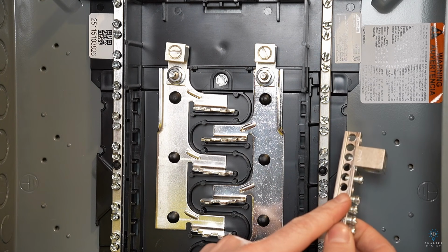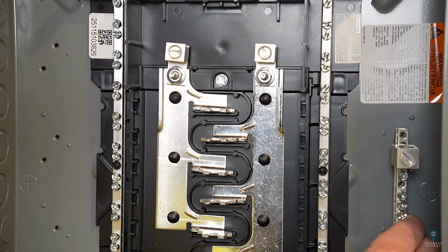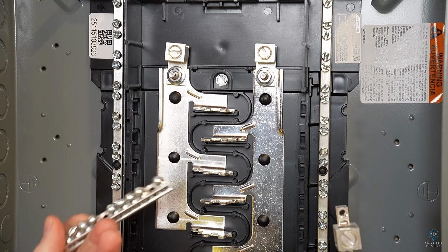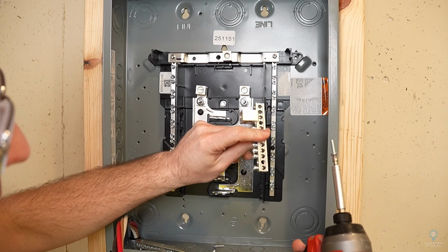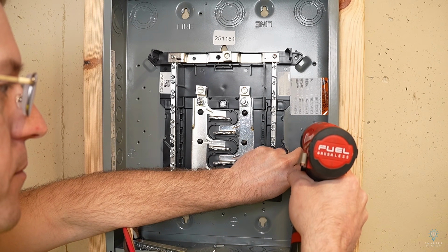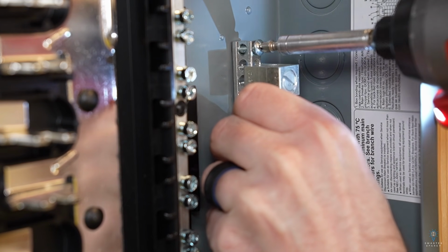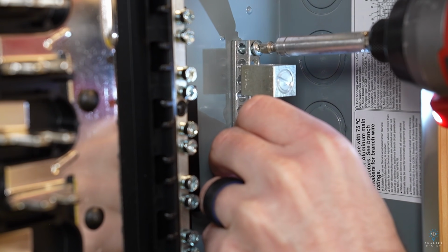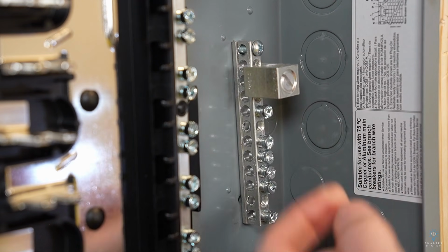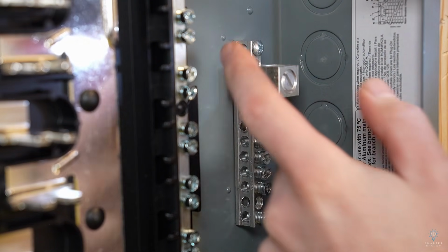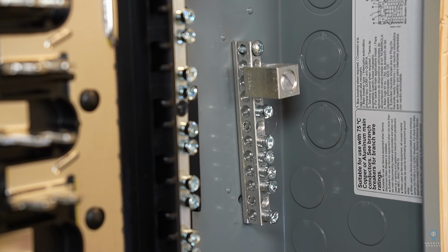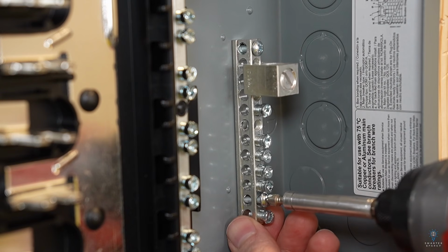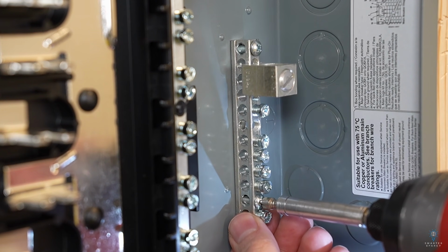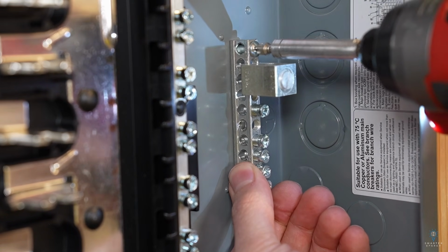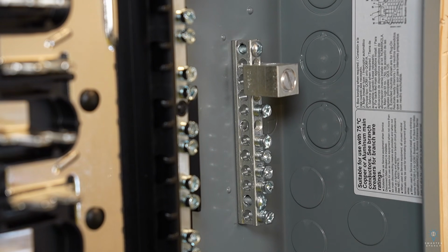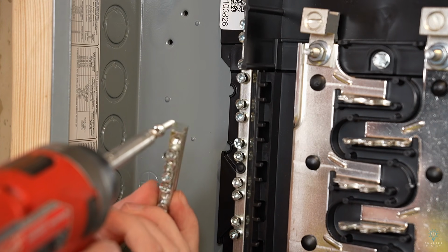So I'm going to install the ground bar with the terminal lug on it on this side of the panel. Then I'm going to install this other bar on the left side of the panel. So I'm going to grab this bus bar here with the lug on it and screw in the top screw. These screws are a very tight fit. So that took quite a bit of torque and it's still loose. So we'll go through and we'll tighten everything up once we get this bottom one put in as well. That bottom one is tight. And that top one is tight. And man, is that loud. And we'll do the same on the left side.